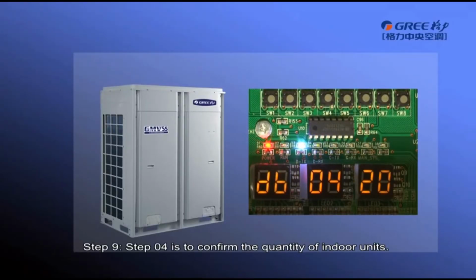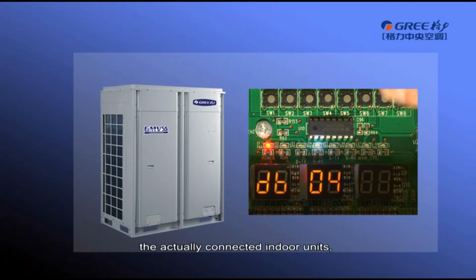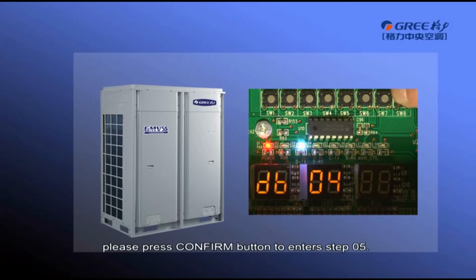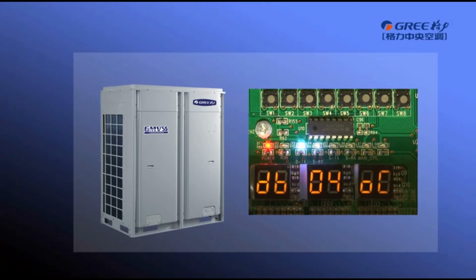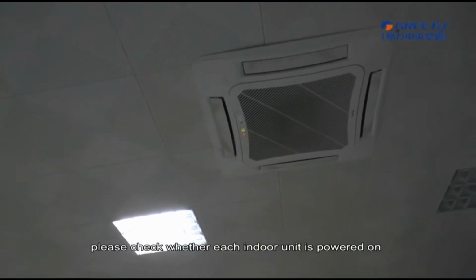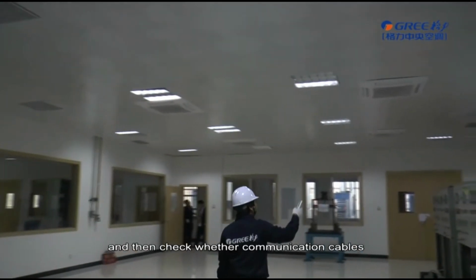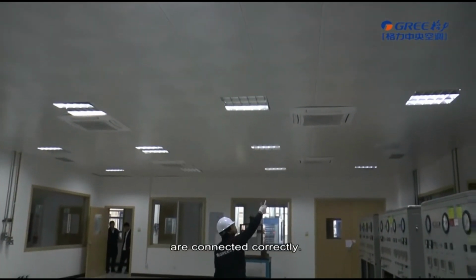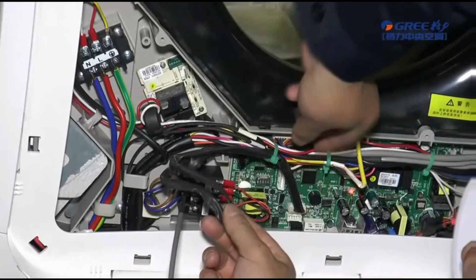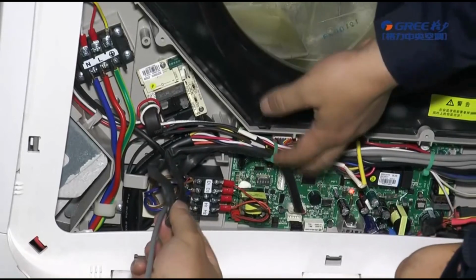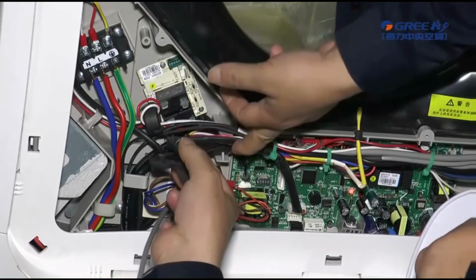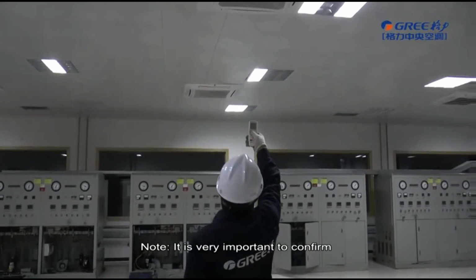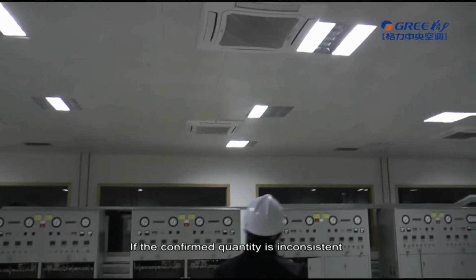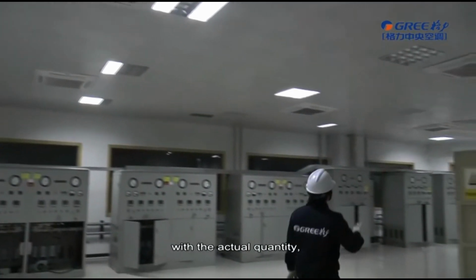Step 04 is to confirm the quantity of indoor units. If the displayed quantity is consistent with the actual connected indoor units, please press confirm button to enter step 5. If the displayed quantity is inconsistent, please check whether each indoor unit is powered on, and then check whether communication cables are connected correctly. It is very important to confirm the quantity of indoor units. If the confirmed quantity is inconsistent with the actual quantity, the system will run improperly.